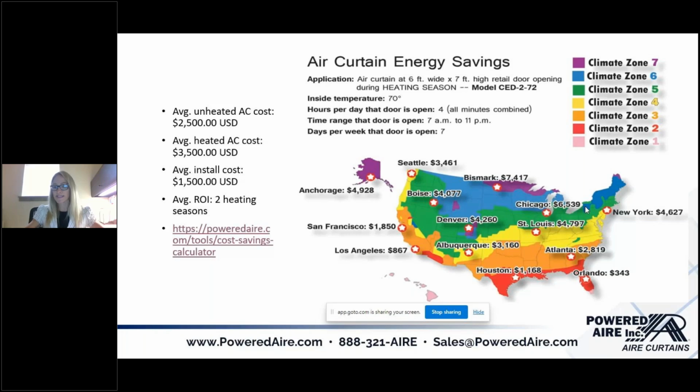So you can see New York, $4,600, Chicago, $6,500. And just for reference, an average unheated cost for an air curtain, maybe $2,500 for this size. If you add electric heat, $3,500. Average install cost about $1,500. So again, about a 2 heating season return on investment.